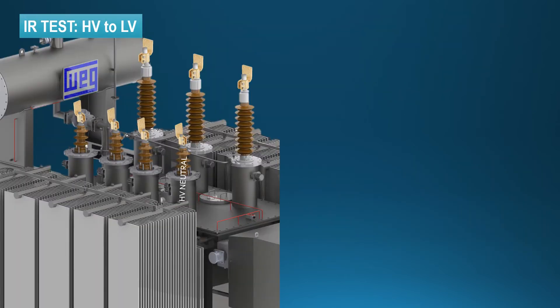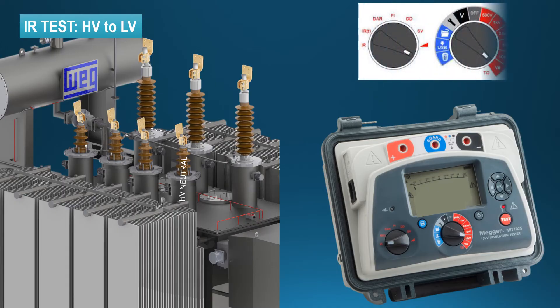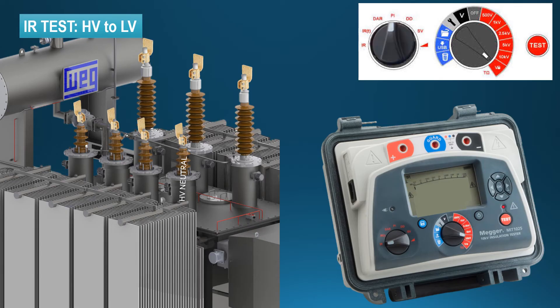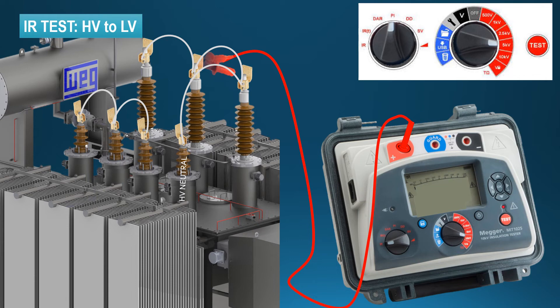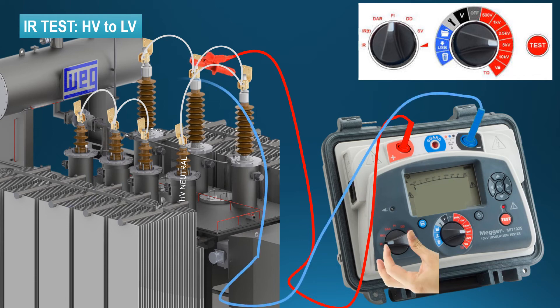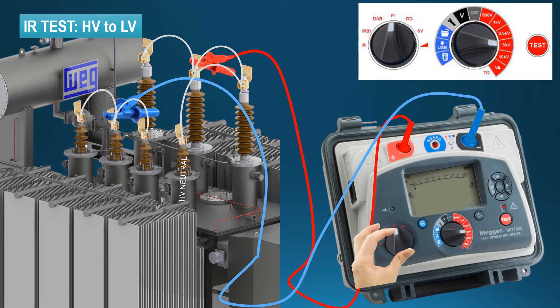IR test procedure, HV to LV. Polarization index PI to be measured at 5 kV, from which IR insulation resistance value will also be available. After 10 minutes.